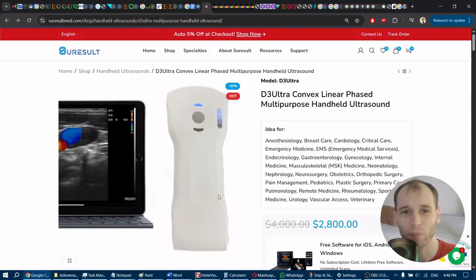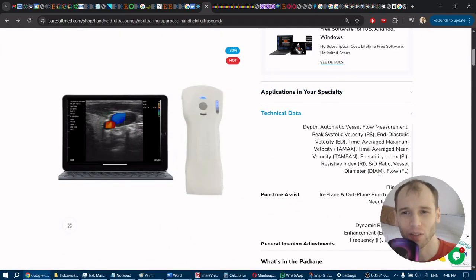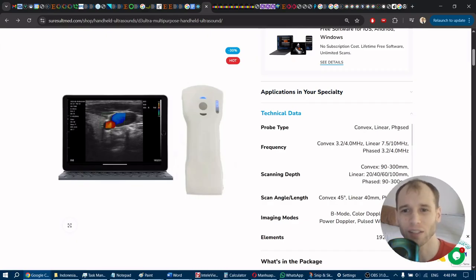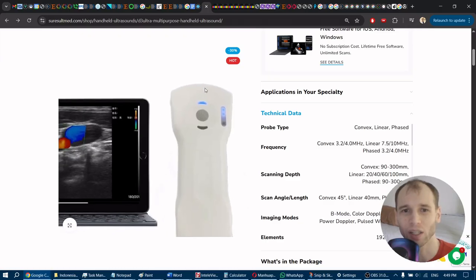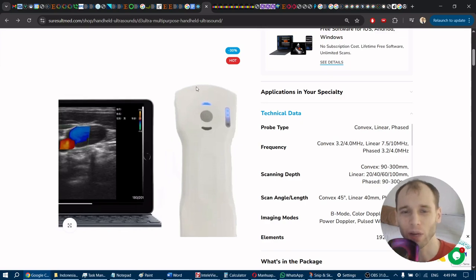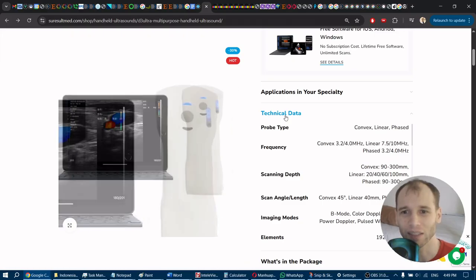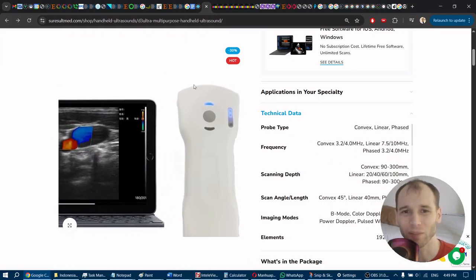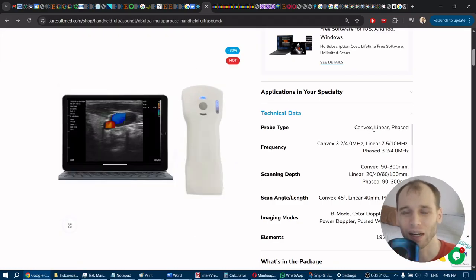So let's go through some of the specs for this unit. If we go to detail here, we have a convex, linear, and phased. How they do the phased or the sector probe is it's basically just part of the convex probe. You turn off the elements left and right of center, and you just focus on some of the elements in the center of the curvilinear portion, and you can basically turn any curvilinear into a phased array or a sector probe. But keep in mind you're limiting your capabilities when you limit how many elements you are using. So there are limitations to its phased mode or sector probe mode. It is nowhere close to as good as the convex or curvilinear mode, nowhere close to as good images.